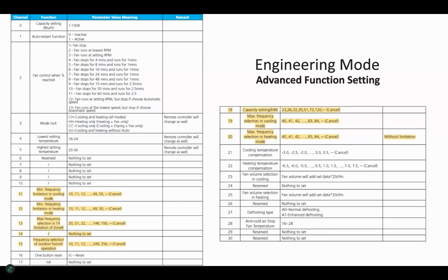There's no list. I have no idea what the factory defaults are. I know one, which is number two, which is probably fan run. I think it comes out as either 2 or 3, it runs either the setting RPM or the lowest RPM. That's the only one I know, as far as the rest of them, and auto restarts out of the box. Most of these are set default, so like your lowest temperature setting is 16, your highest temperature setting is 30, that means 60 and 86 in Fahrenheit.